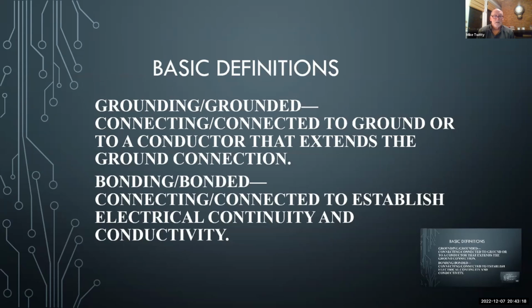Okay. Bonding and bonded is connecting or connected to establish electrical continuity and conductivity. Let's think about that for a minute. If you're tying a bunch of conductive equipment together through a conductor, whatever it be, then you're bonding. There are proper ways to do that, and we'll talk about that. But it's basically putting everything in contact together to establish electrical continuity and put it all at the same voltage potential. That's the main important thing.